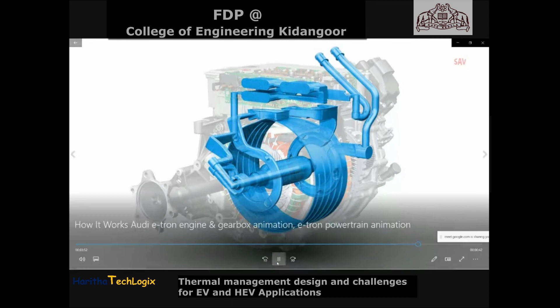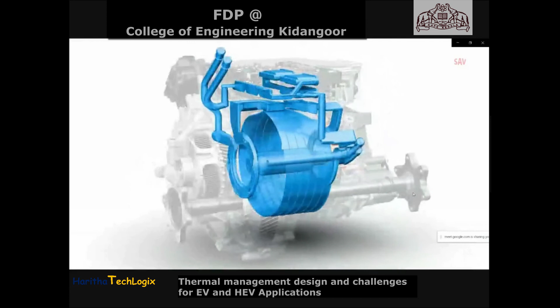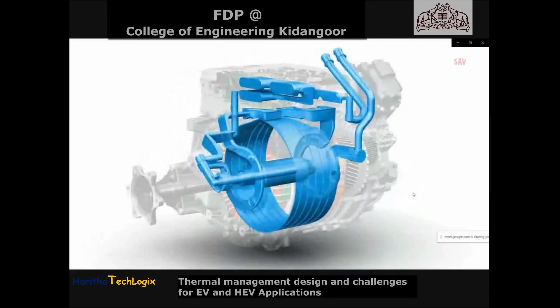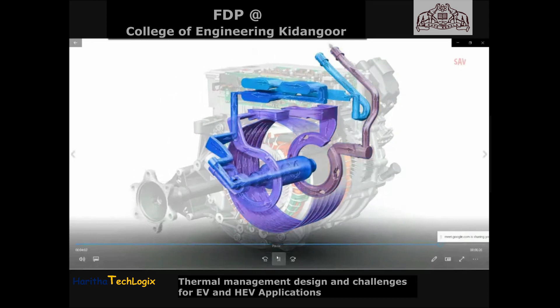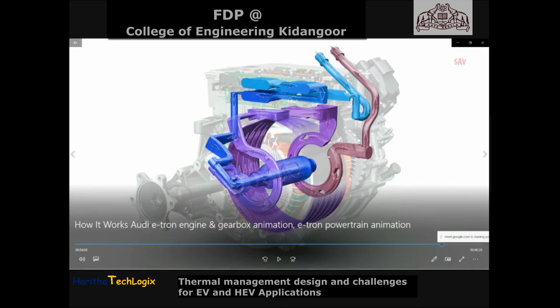So we see that the coolant circulation follows this path: it comes into the inverter module and first cools down the inverter module, then goes to the rotor component, comes back and rotates to the bearing system. From there it goes to the bearing system and then to the stator component, cooling it down completely. Finally it goes to the other bearing at the other end, and then to the outlet end.